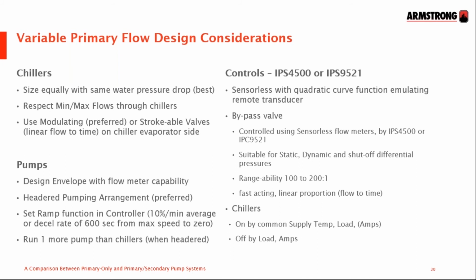So just getting back to the points to look out for on variable primary flow: you can have dedicated pumps with unequal sized chillers or equal chillers with headered pumps. You need to respect and know the minimum flow through the chiller so that you've got your bypass line correctly sorted out. With pumps, design envelope pumps give you that flow meter capability, which then helps to manage the chiller bypass valve operation. The speed ramping up and ramping down times for the pumps need to be set slow to match the performance of the chillers, and the chillers themselves are staged in based on supply temperature, staged out on their load.